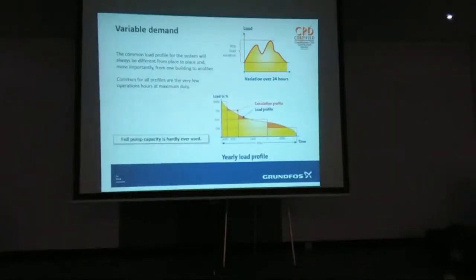It does vary. And throughout the year, you might only want 100% load for a very, very short period of time. I'm sure you've all seen this for even ordinary heating systems. You only want 100% load for 2-3 days of the year maybe. So you get away with a much smaller plant.